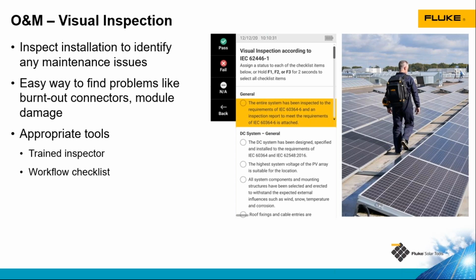Also helps to have a checklist, having that workflow so that they're doing the same procedure for each section of the array or every different system, and making sure they're not missing any issues. The list in the middle of this screen is from the SMFT 1000. This has a visual inspection checklist based on the IEC standard that has about 50 different points that need to be inspected. The SMFT 1000 allows you to say whether each of those points is a pass, fail, or not applicable, and you can save the results right in the tool, download them to the TrueTest software, and report out afterwards without having to do any type of handwritten notes and then transfer that into a digital format. That makes it very easy for saving the results and reporting them out later.